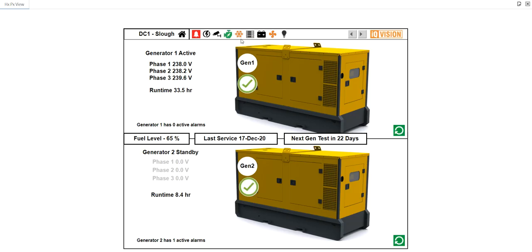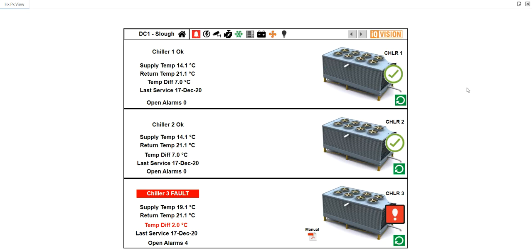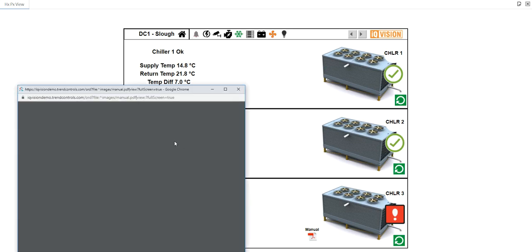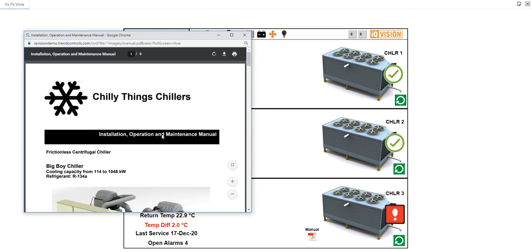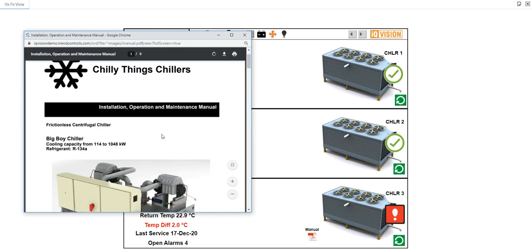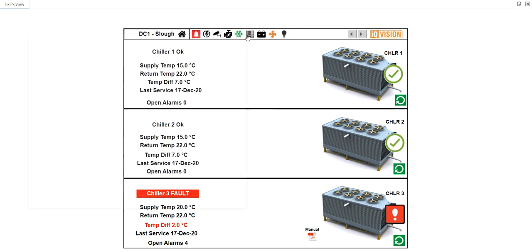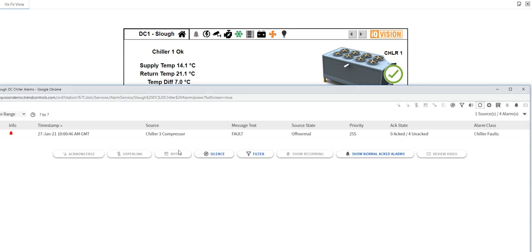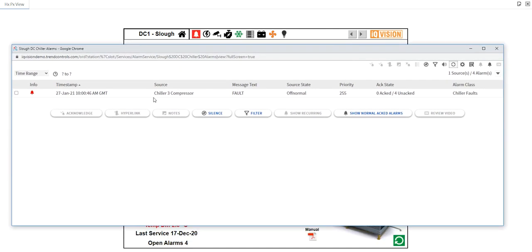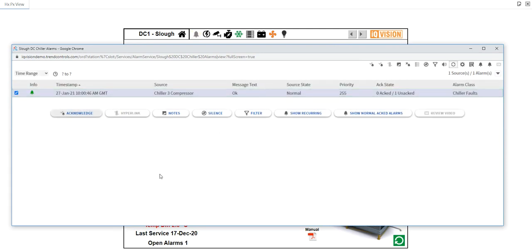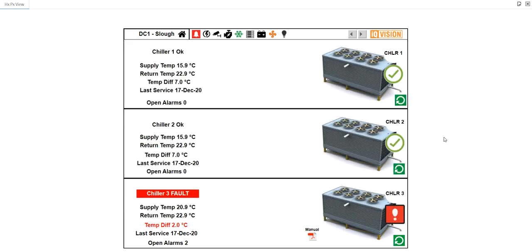If I move on, we're back to the generators. You can see this is now green for good. We'll move on again to our chillers. Once again, we have a big red thing saying something has gone wrong. We can actually refer to the manual down here if we want to. It's just an imported PDF, only placed here to make the operator's life easier so we can go and find it. You'll notice we have the big boy chiller from Chilly Things Chillers, a very well thought of model. We can see we have a fault on Chiller 3 with some open alarms. Hopefully you may have heard the irritating noise there, which tells me there is an alarm. It has a compressor fault. I'm going to acknowledge that alarm and send someone out to go and fix that or at least look at it. It's in fault. So that's going to need looking at. I won't bother resetting that one here.